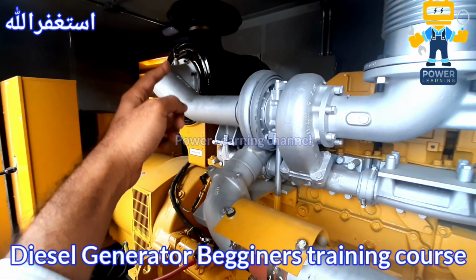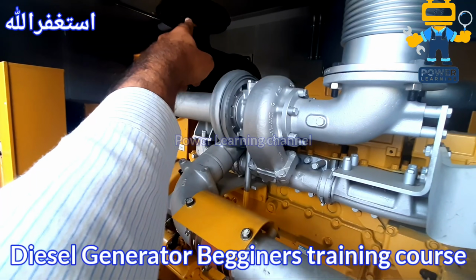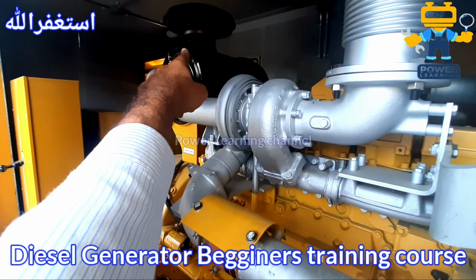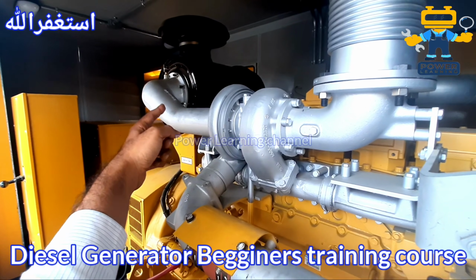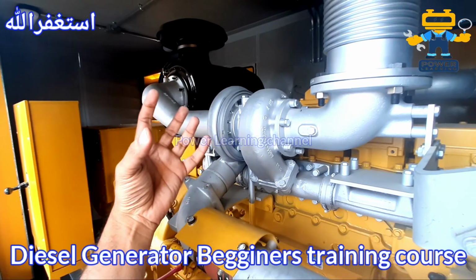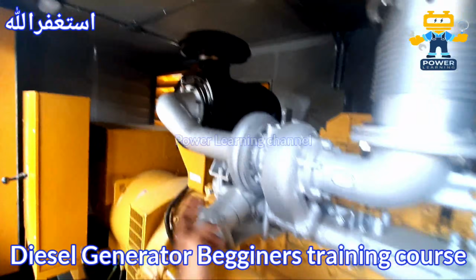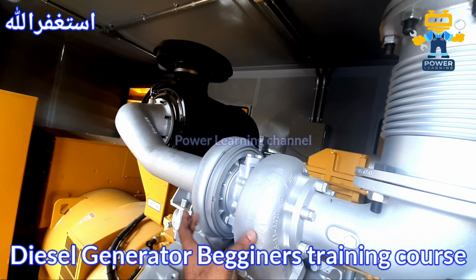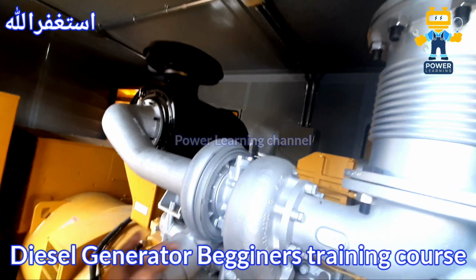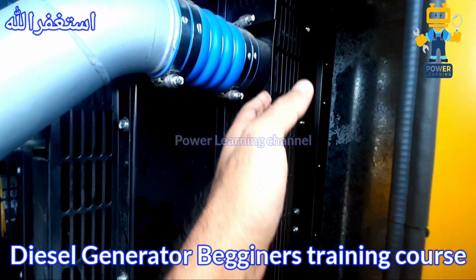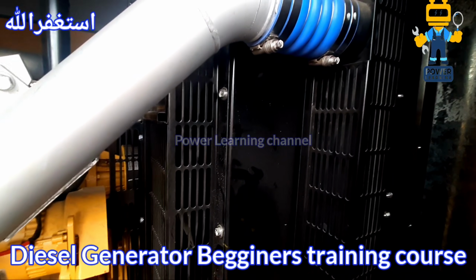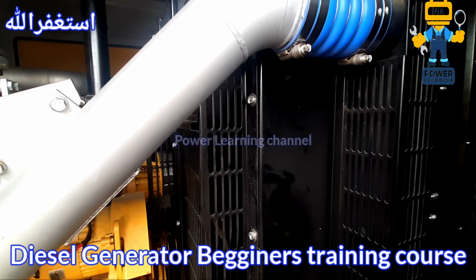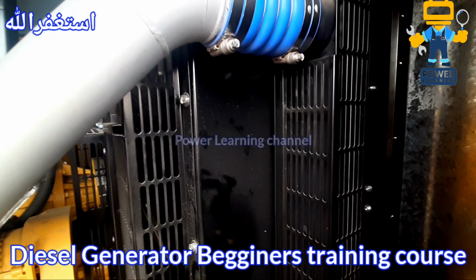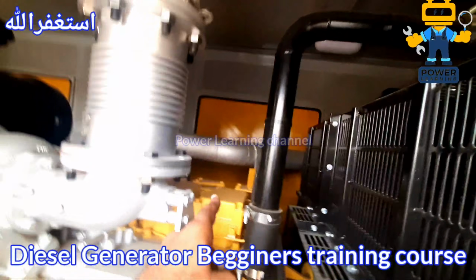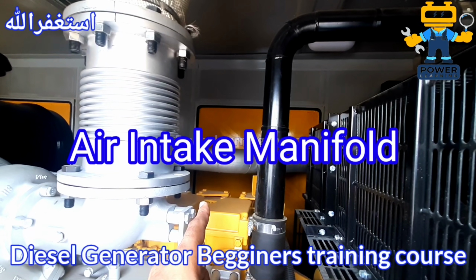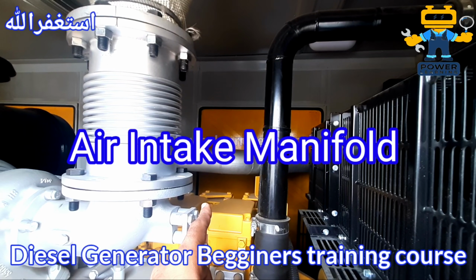Let me repeat how the air system works. The fresh air from the environment enters the air filter, then passes through the air filter element and gets cleaned. The clean air enters the turbo housing. From the turbo housing it is pressurized and goes to the aftercooler. The aftercooler looks like a radiator, but only for air; there is no water. When the air gets cool, it enters the combustion chamber from the other side.